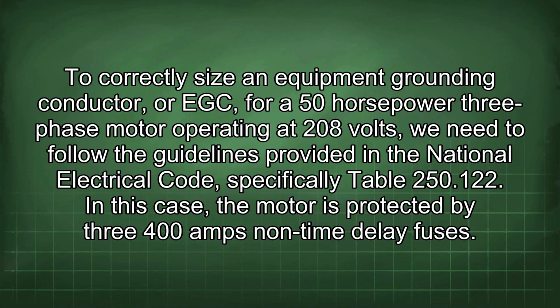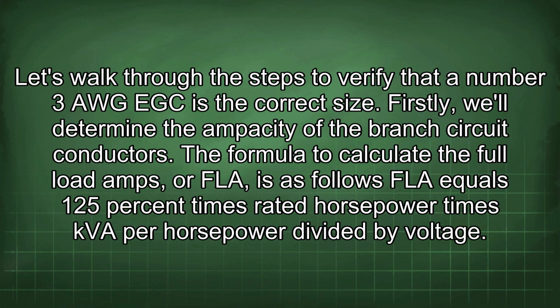To correctly size an equipment grounding conductor, or EGC, for a 50 horsepower three-phase motor operating at 208 volts, we need to follow the guidelines provided in the National Electrical Code, specifically Table 250.122. In this case, the motor is protected by three 400 amp non-time delay fuses. Let's walk through the steps to verify that a number 3 AWG EGC is the correct size.